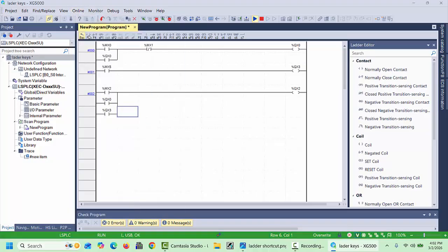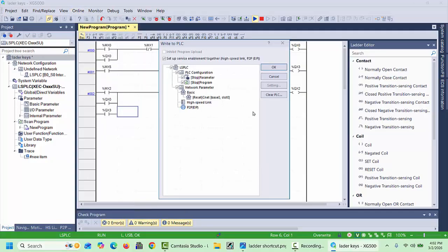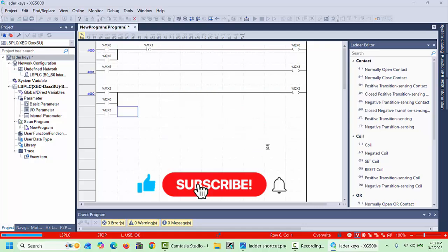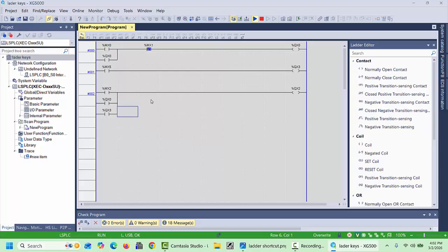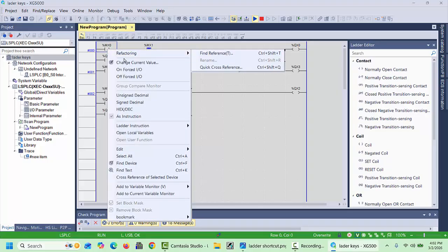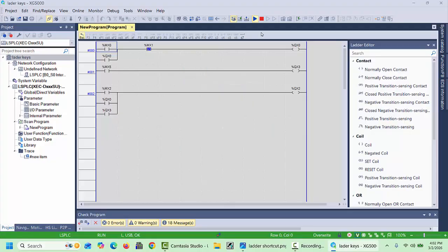We just have to connect our PLC with the PC, and after that we will write the program into the PLC. Now our program is completely downloaded to the PLC, and click OK. We will monitor the program, and you can see I will operate the MX0, and after that you can see our QX0 is operated. But the function we designed here is that when our QX0 is on, our QX2 also needs to be on. We defined it here, QX0, with this program.